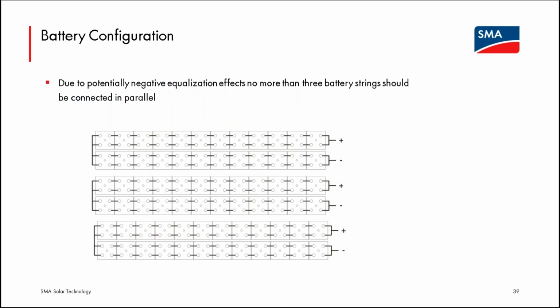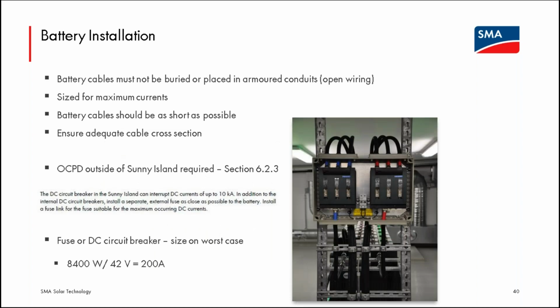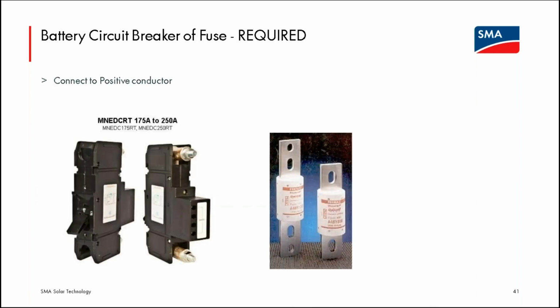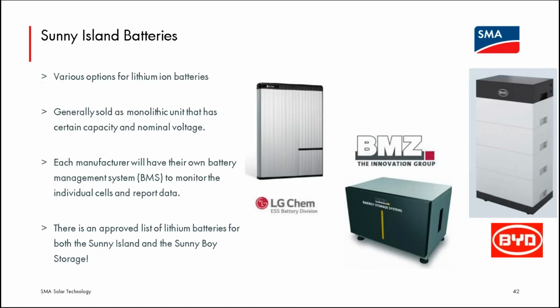So SMA recommends no more than 3 strings going to a Sunny Island cluster. So that generally will limit your battery bank capacity size. And most likely it will be significantly smaller than 10,000 amp hours. And this is showing the breaker or fuse between the island and battery bank requirement. And Midnight Solar, again, makes DC circuit breakers that fit the correct sizes quite well.